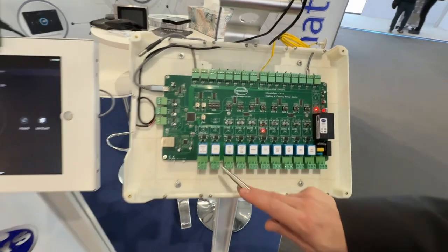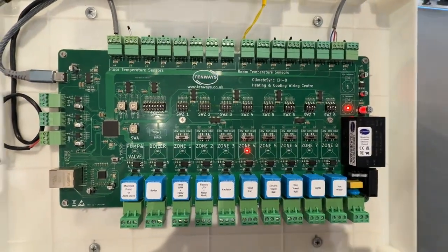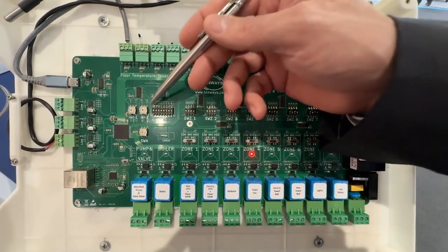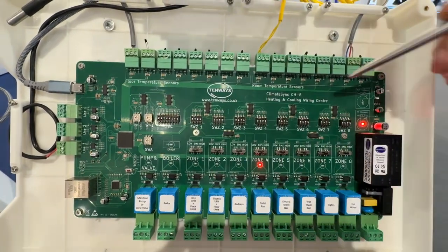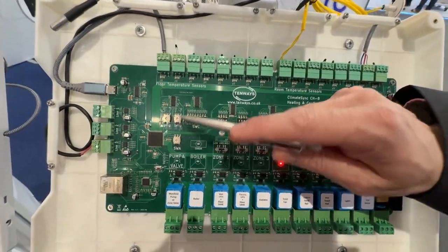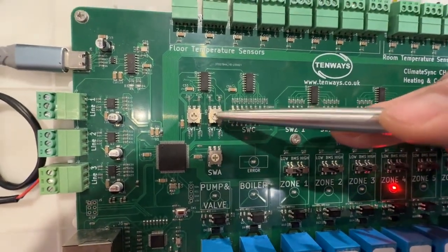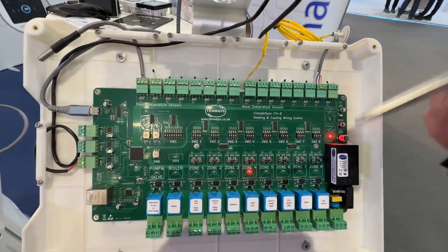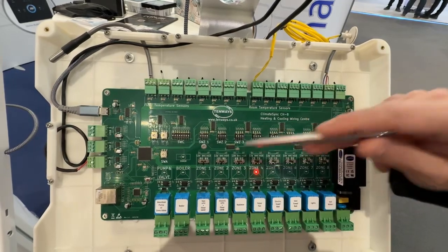Each relay on the wiring center has a voltage-free, normally open, normally closed connection. Many configurations can be done from the dip switches for the zones or for the entire board, and rotary switches as well. The rotary switches will allow you to set the address of the board or to set the floor limit required for the entire board. However, if you need individual floor limits as well as many other settings, hundreds of them, we can do those settings from the board itself.